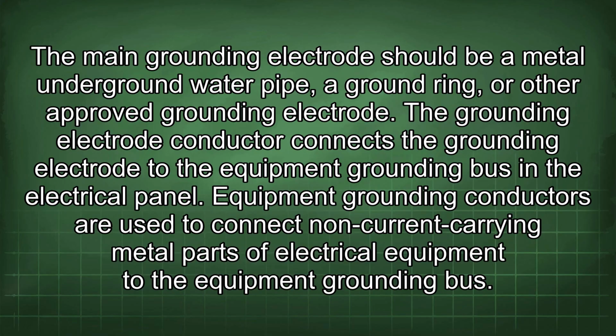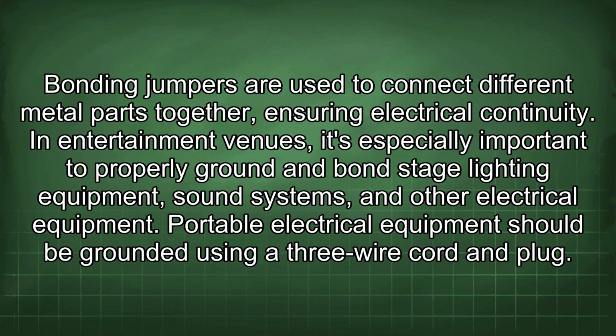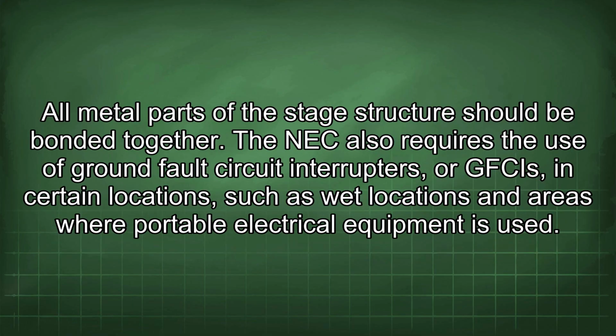The main grounding electrode should be a metal underground water pipe, a ground ring, or other approved grounding electrode. The grounding electrode conductor connects the grounding electrode to the equipment grounding bus in the electrical panel. Equipment grounding conductors are used to connect non-current carrying metal parts of electrical equipment to the equipment grounding bus. Bonding jumpers are used to connect different metal parts together, ensuring electrical continuity. In entertainment venues, it's especially important to properly ground and bond stage lighting equipment, sound systems, and other electrical equipment. Portable electrical equipment should be grounded using a 3-wire cord and plug. All metal parts of the stage structure should be bonded together.